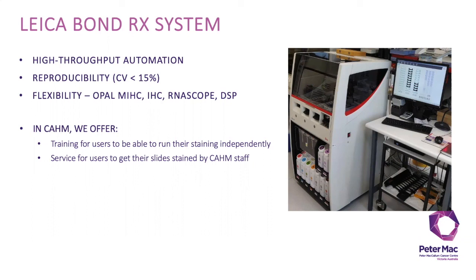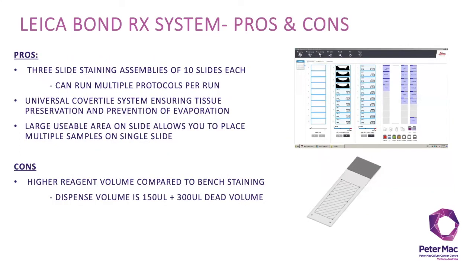In CAHM we offer training for users to run their staining independently, and we also offer a service for users to get their slides stained by CAHM staff. Some of the advantages of the Bond system is that you can run multiple protocols per run as it contains three separate slide staining assemblies. So you can simultaneously run, say, ten seven-plex slides on one SSA, your library slides on another SSA and monoplex slides on the third. The Bond RX has a universal cover tile system which facilitates gentle, even reagent flow onto the tissue and also prevents evaporation of reagents. Furthermore, the large usable area on the slide enables you to place multiple samples on the slide, which provides cost benefits. However, one of the disadvantages of the system is that it has a higher reagent volume compared to manual staining on the bench — it has a dispense volume of 150 microlitres and also a 300 microlitre dead volume.